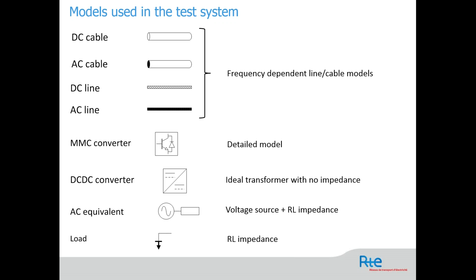So this is the converter station configuration. As I mentioned previously, it's made using the MMC topology. The main idea of the topology is provided here. You have several submodules connected in series. A group of submodules represents one valve or one arm, and at the end you will end up with 6 valves or 6 arms, and each 2 arms are connected to the AC side.